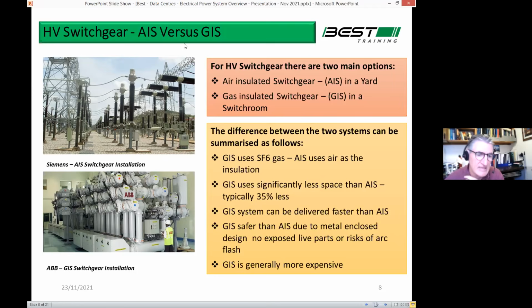Again, this is usually built by the data center operator. Facebook in Clonee, which probably a lot of people know about, just to give you an idea, I worked on the first phase of that, which was 3 buildings, and the first connection was 120 megawatts. That was for phases 1, 2, and 3. They're now building phase 5, I think, or phase 6, if I'm not mistaken. They have a massive air insulated switchyard like that, and at this stage they probably have 200 megawatts of capacity on the site. So it's just phenomenal.